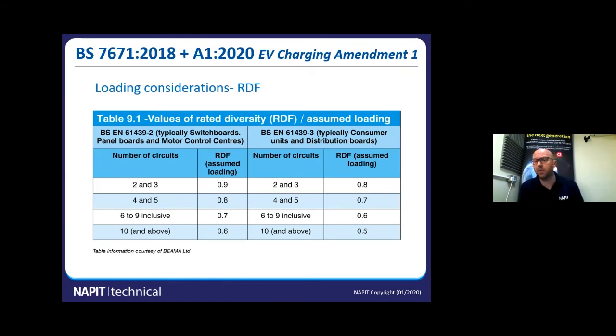So we need to think about this from the design stage, and what you really need to do is have a look at the distribution board and see what different ways you can configure that to make sure that you've not got the EV charging next to a circuit that is continuously loaded, and then you won't have any simultaneous loading effects on that EV charge point. You can talk to the manufacturer of the consumer unit. They may be able to tell you about other configurations that you can use. Again, we've covered this in depth in the on-site solutions.